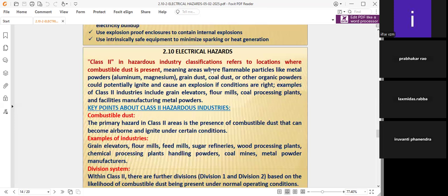This means areas where flammable particles, like metal powders, for example aluminum, magnesium, grain dust, coal dust, and other organic powders, could potentially ignite. That means the atmosphere itself, the oxygen in the atmospheric air, could cause self-ignition. It will be ignited, burned, and cause an explosion when the conditions are right. What is important here is that the circuit itself is taken care of, with its circuit breaker, or that at the source itself dust generation is not much, or a dust extraction system is properly installed. That's very important in this area.